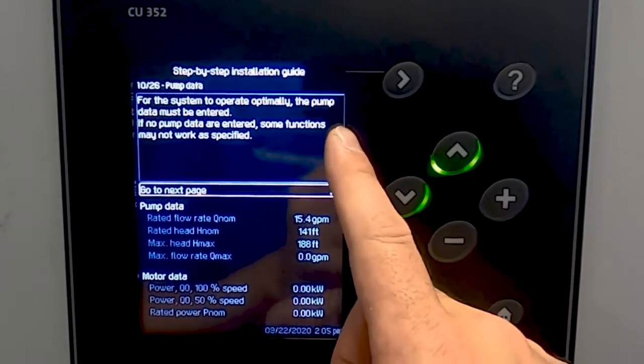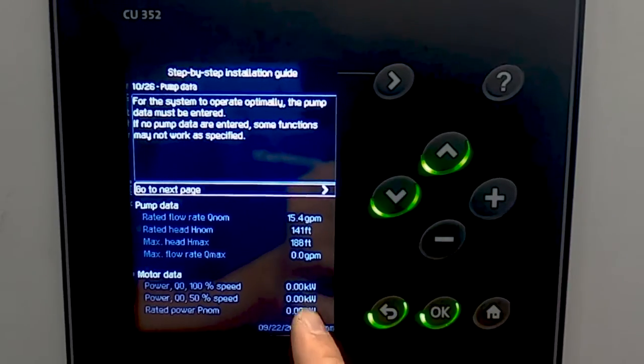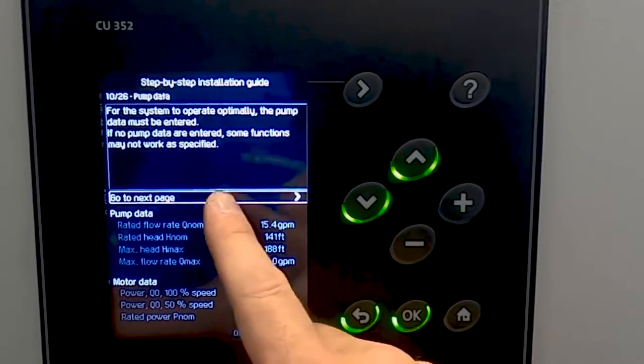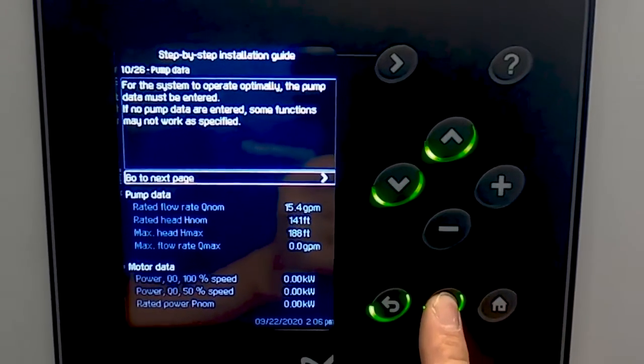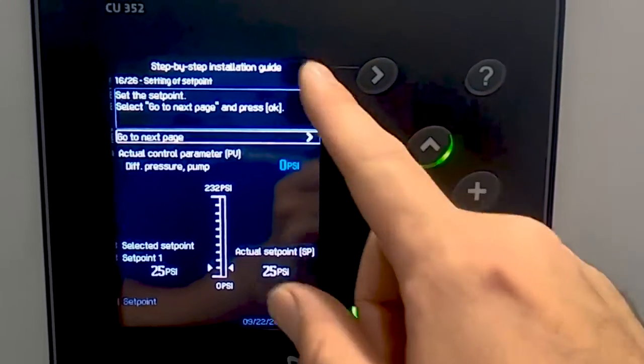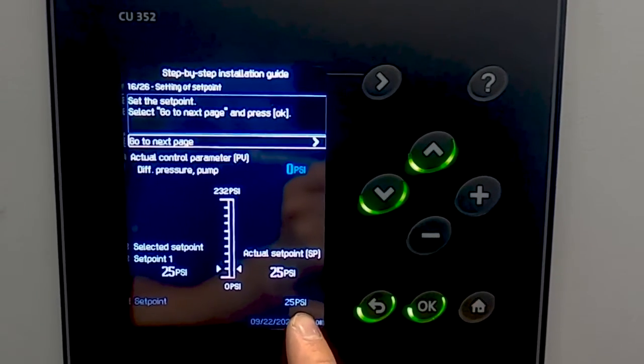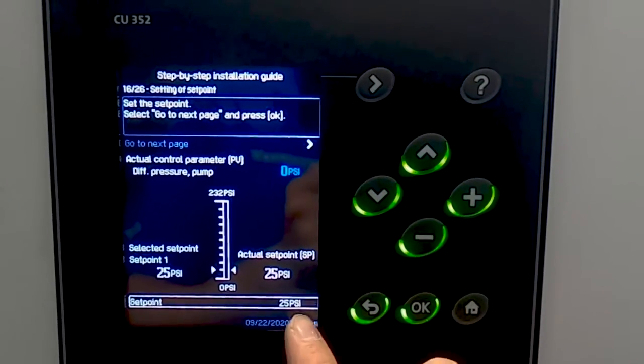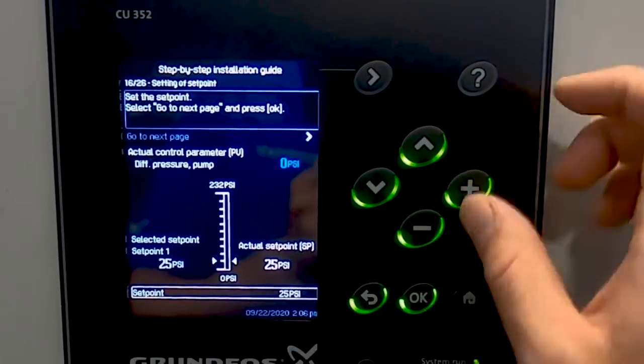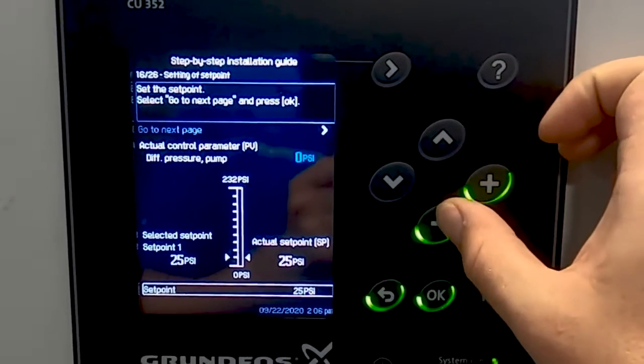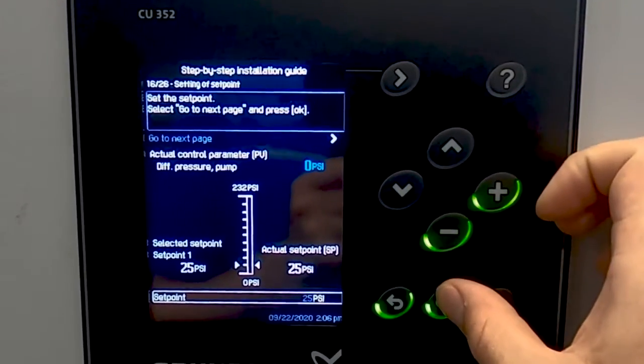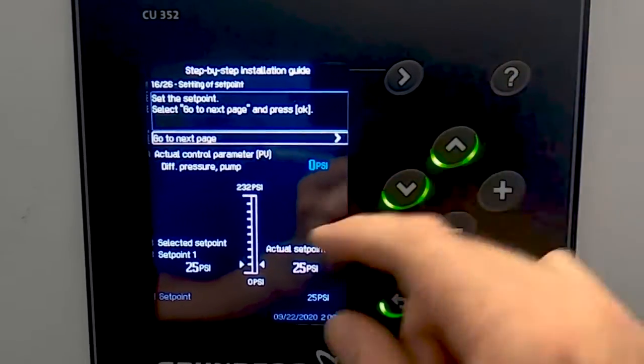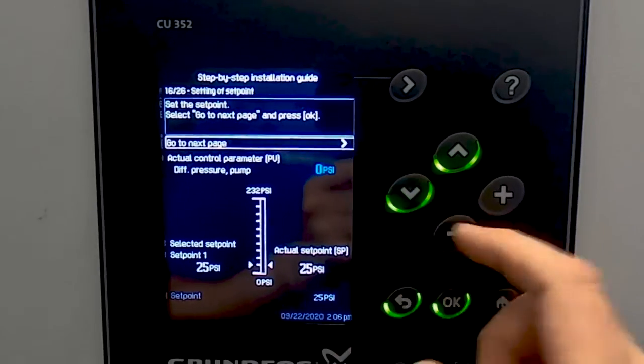The next option is regarding the pump data — this is all preloaded from the factory, so these do not need to be adjusted, but you have the option if you'd like. From here, you can follow on to the next page. This step is actually setting up the differential pressure you'd like the system to maintain. For our system, we preset it based on 25 psi. If you hit the arrow down and come to set point, you can hit plus or minus to change that set point. Once we are happy with 25 psi, we say OK and go to the next page.